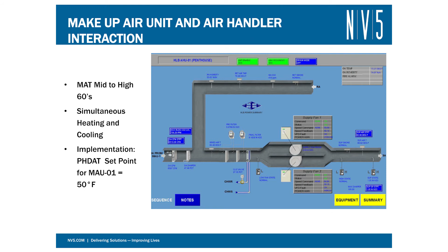Because once the units mixed that air with the return air from the building, which was about 72, 73 degrees, we were seeing mid to high 60s for the mixed air temperature, and then the cooling coil had to re-cool that air back down to the temperature of that unit. So we were definitely seeing some of that simultaneous heating and cooling.